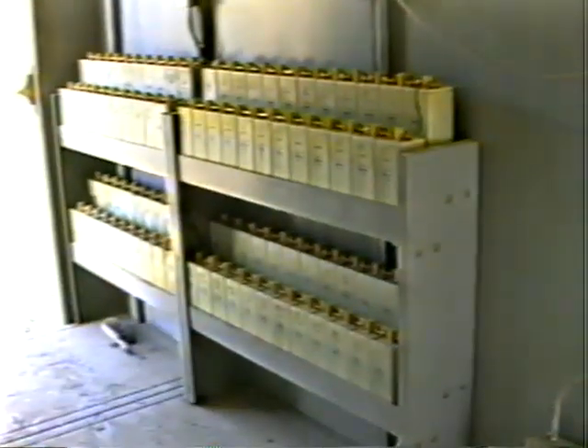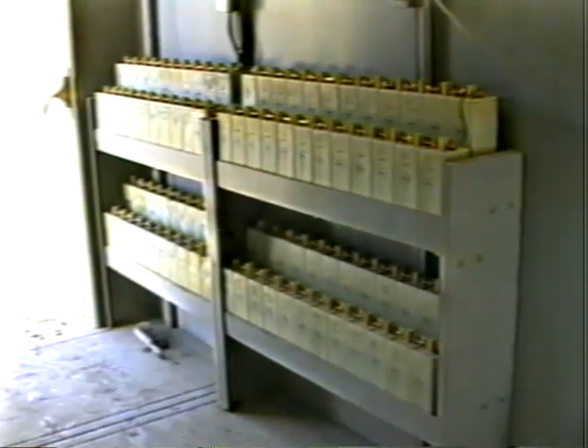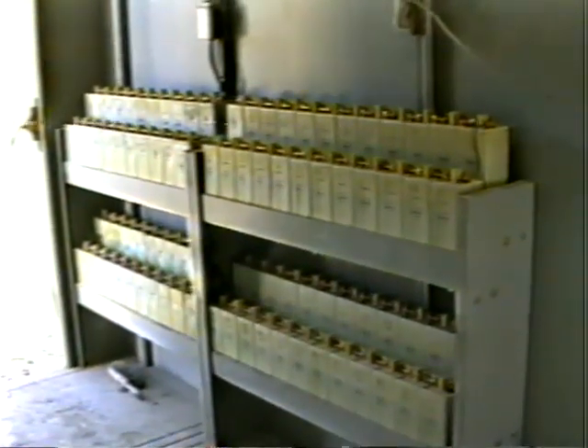We have the truck shop feeder, which also feeds the tailings area. We've got 2 feeders that feed the concentrator, and then we've got 1 feeder that feeds the crusher, because they're all battery backed up. These batteries also feed the main incoming switch. Features include ground fault protection, overcurrent, undercurrent, and phase imbalance.